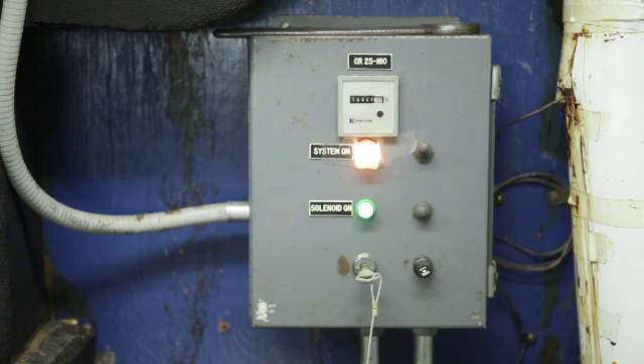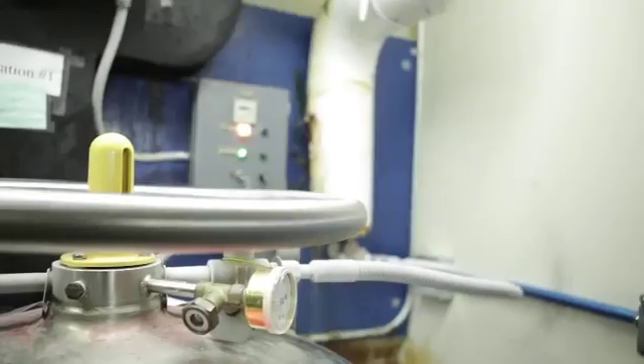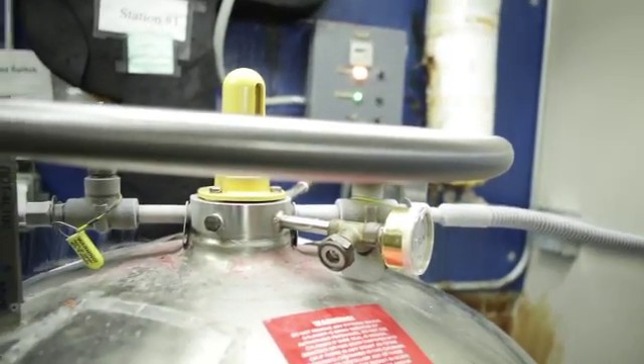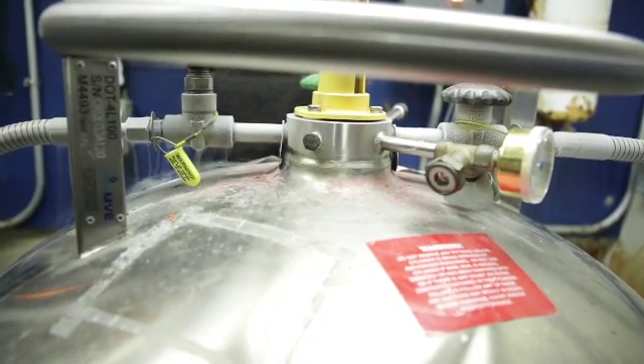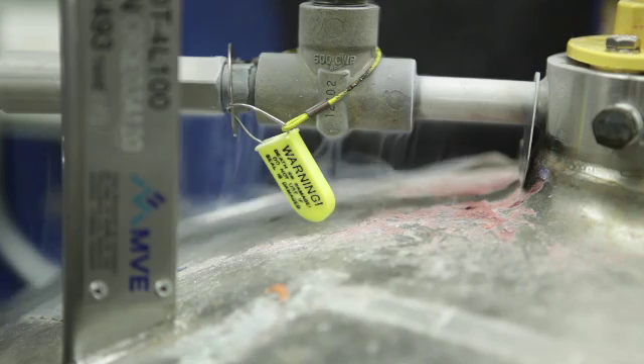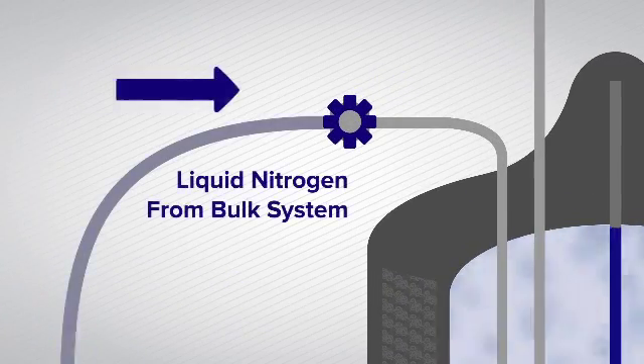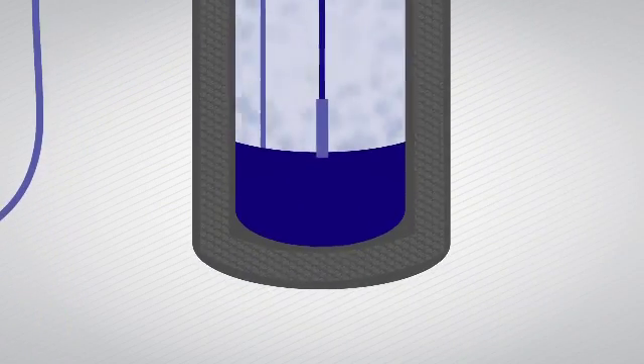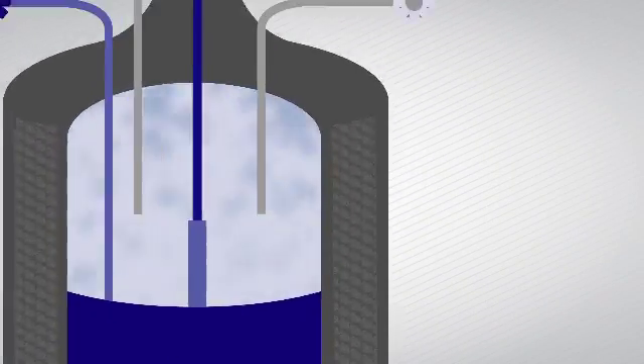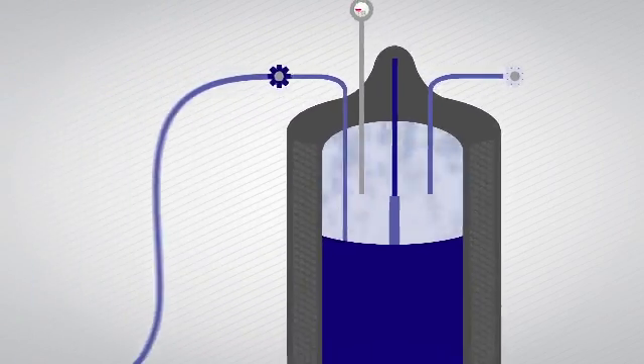Step 5: Monitor the flow. Normally, your liquid nitrogen tank will take approximately 30 minutes to fill. If the filling stations haven't been used recently, it may take as long as one hour. Liquid nitrogen from the bulk system will flow down the inside dip tube of the tank and fill it. Excess gas exits through the vent line. The physical principle is that liquid will always flow from a vessel of higher pressure to a vessel of lower pressure.